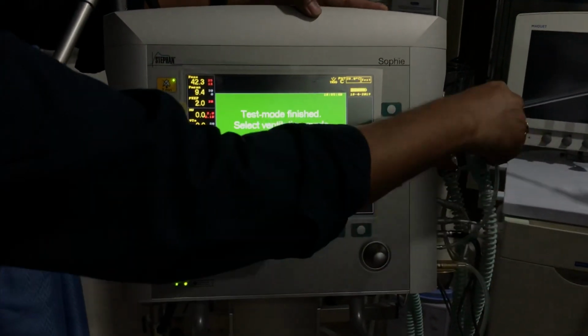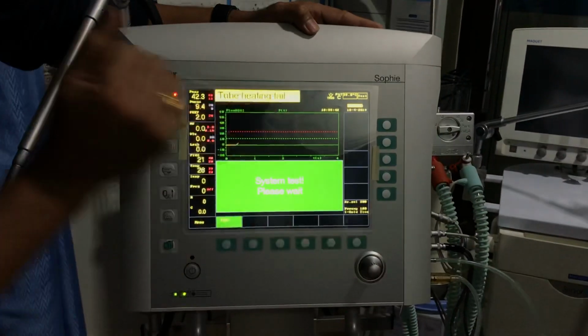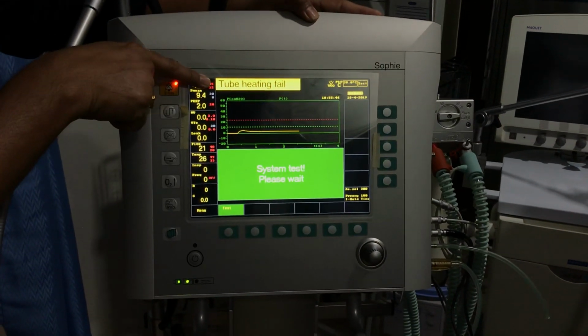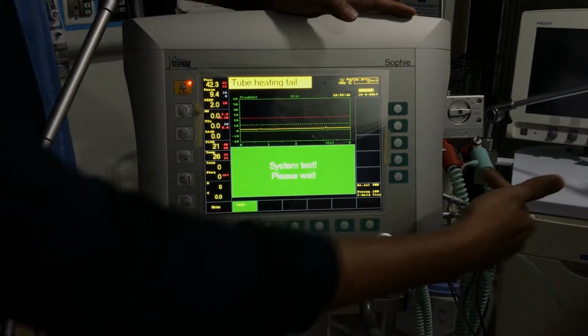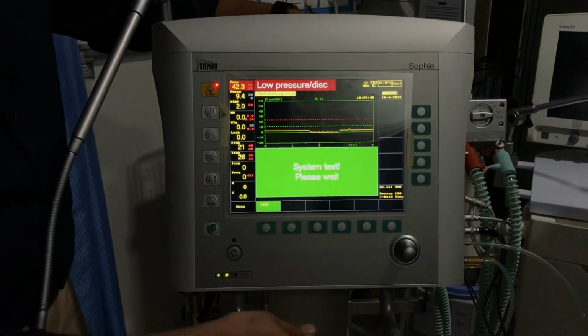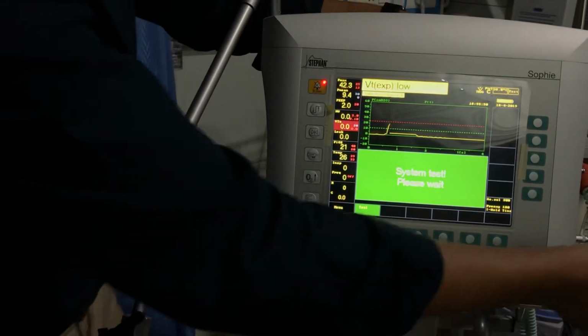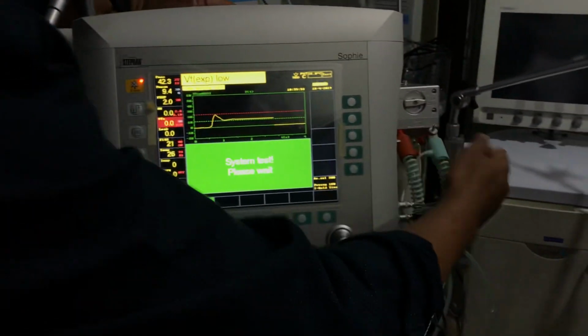Let us say I have not connected this heater wire of the tube, and I try to conduct the test. Immediately you get a message, tube heating failed. That means the heater wire of this tube is not proper, so I have to reconnect it. Humidifier is inbuilt over here.